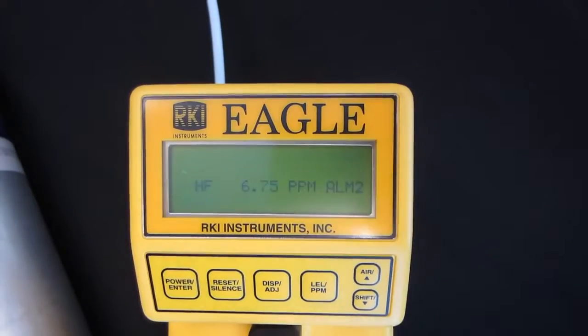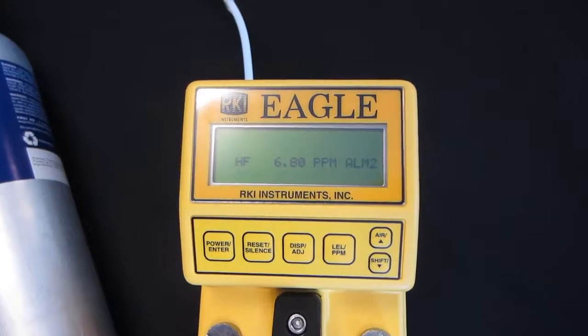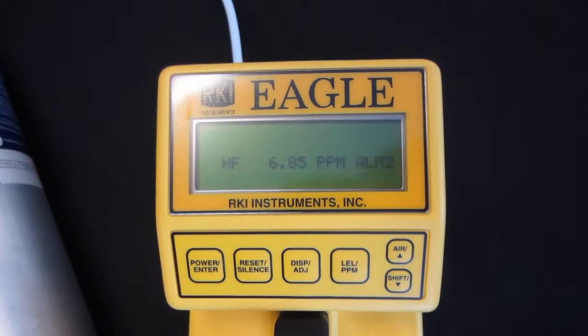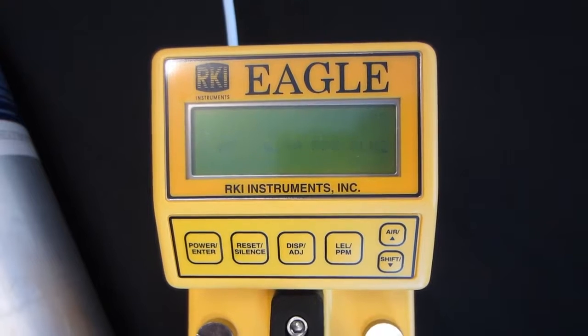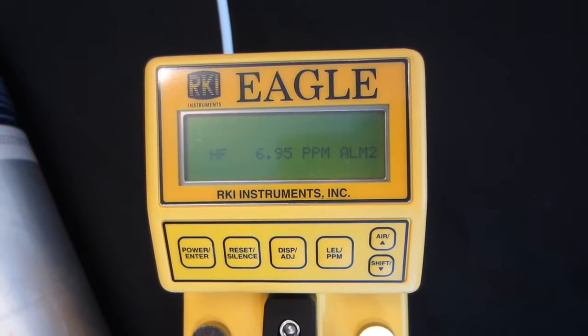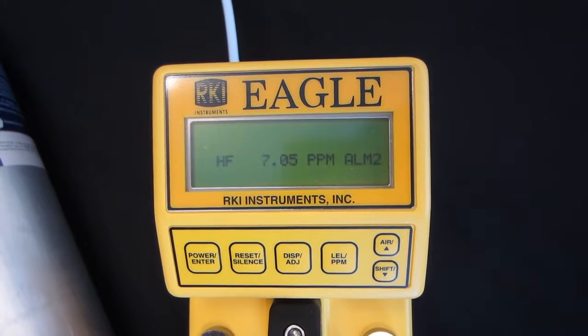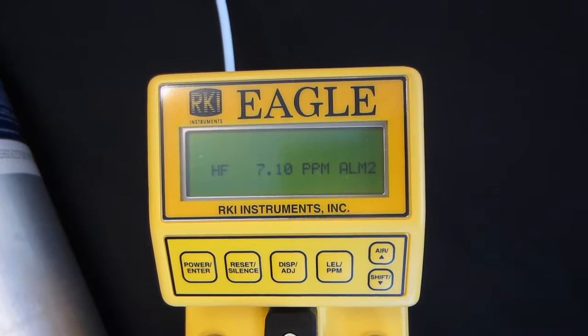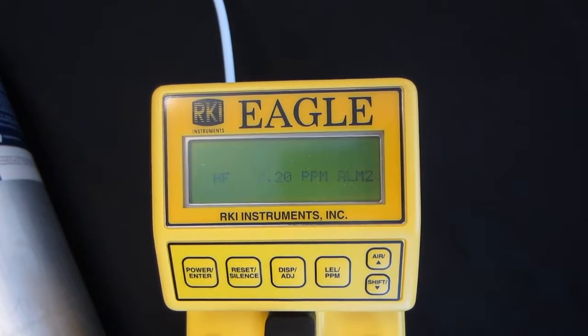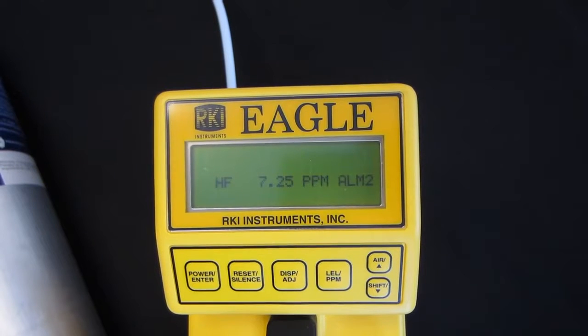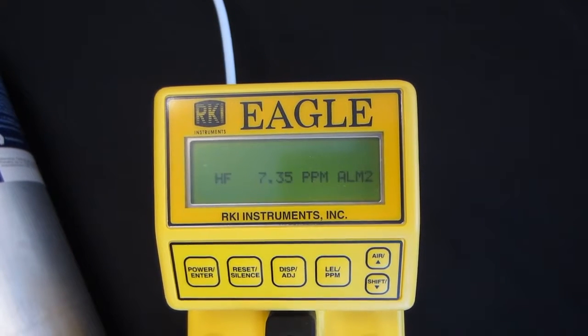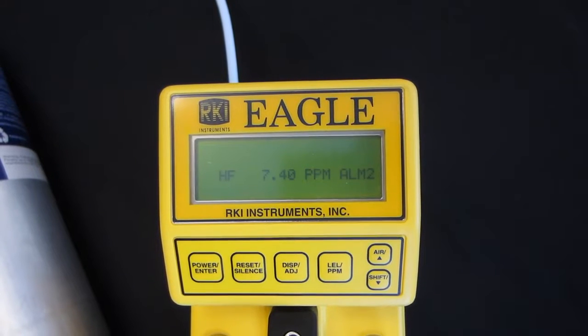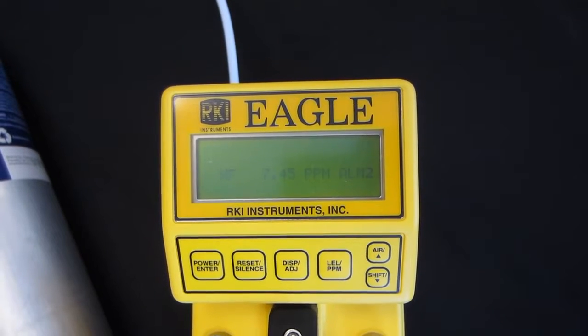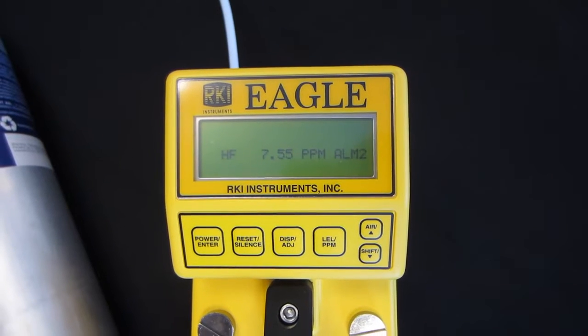So usually you will see the display deflect quite rapidly in the beginning as it climbs up, but as the unit gets closer to its final response, it will start slowing down. Okay, we've been flowing for 1 full minute now, and the unit's at 7.5 ppm out of 8. That's not too bad, really.